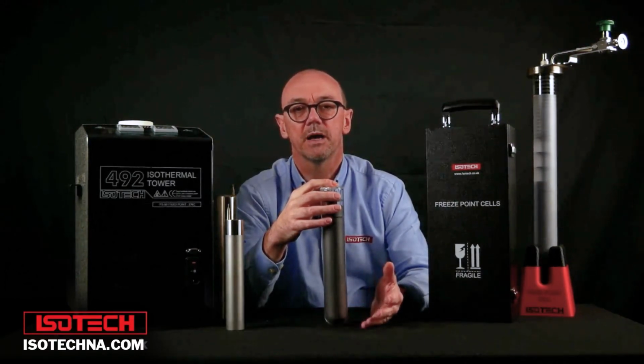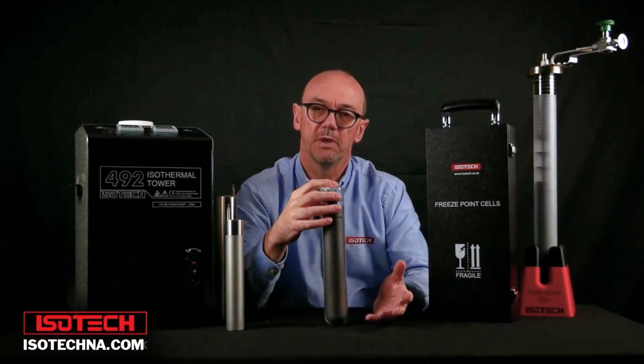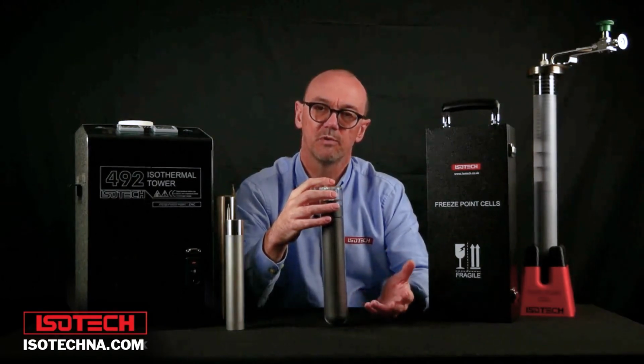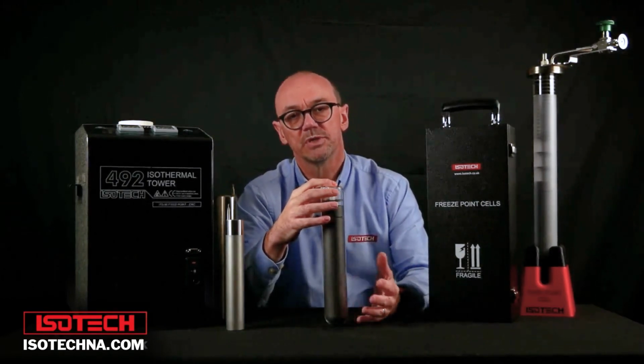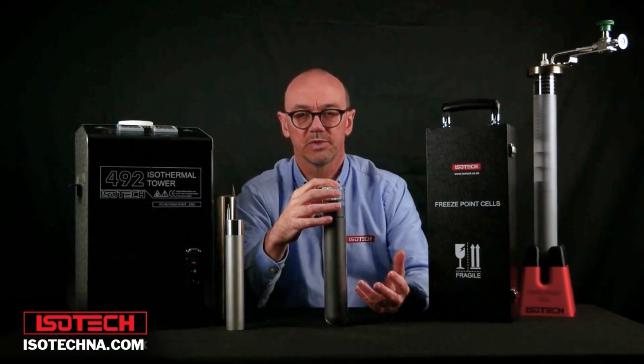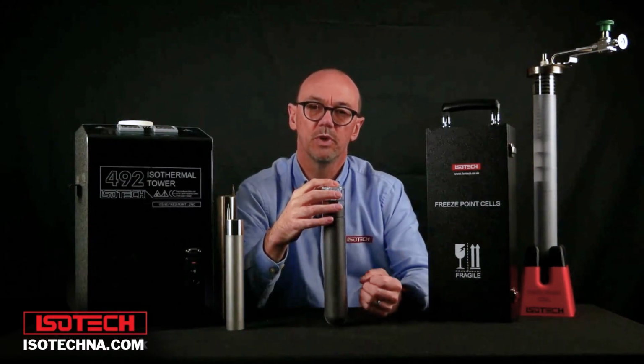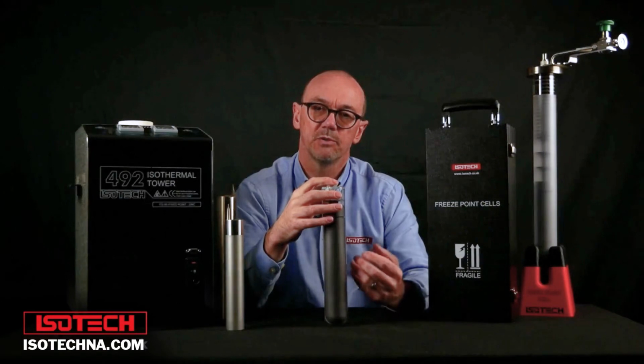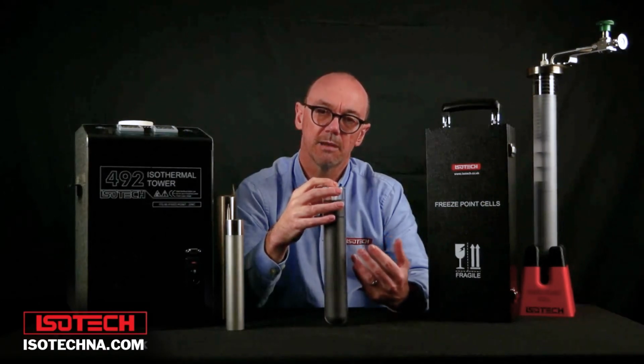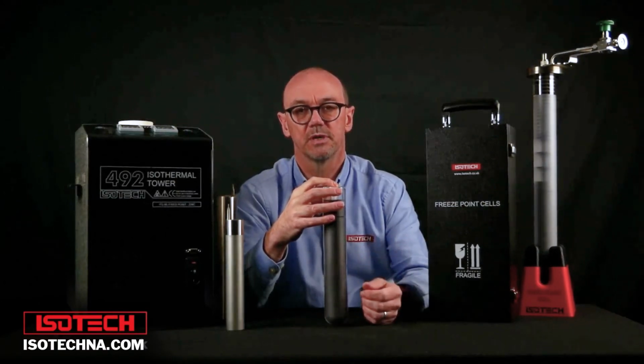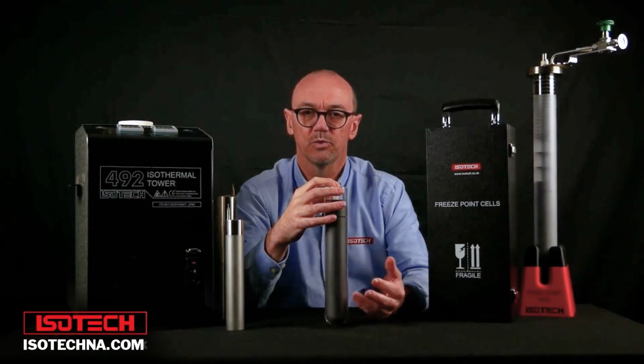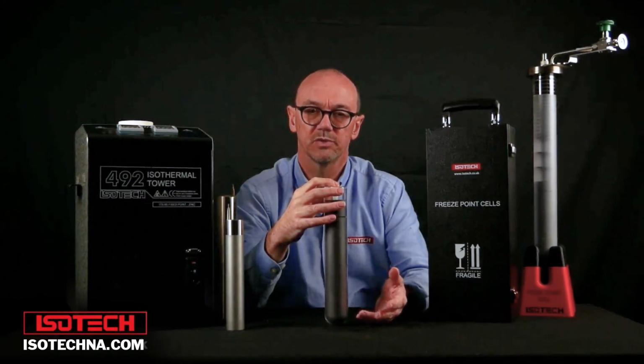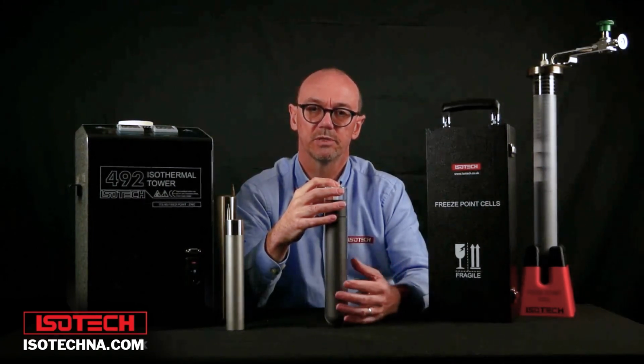Now certainly in the past, the majority opinion was probably no, it's a fundamental constant of nature. But today, in the ISO 17025 world, we need traceability. And so cells need to be calibrated compared to a reference cell. So it's usual now for all cells to have some sort of calibration certificate to establish the traceability.